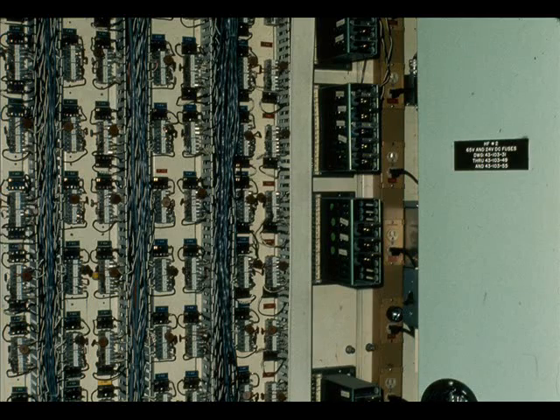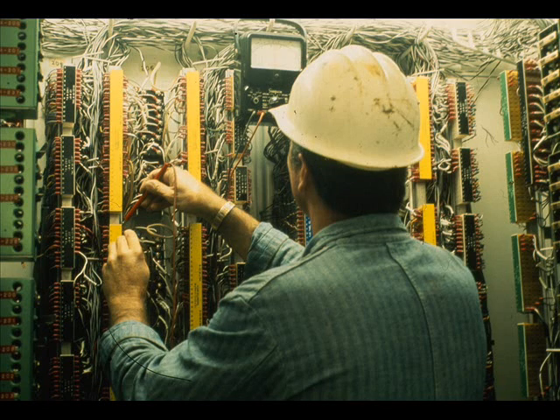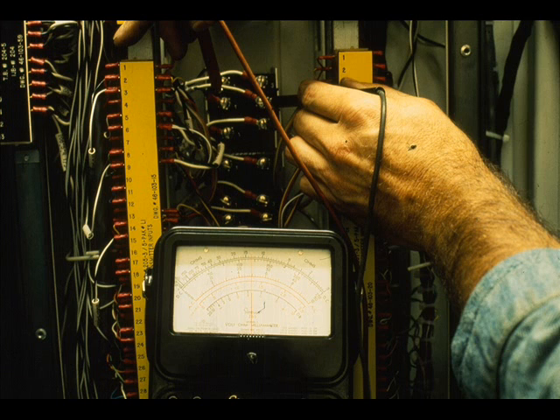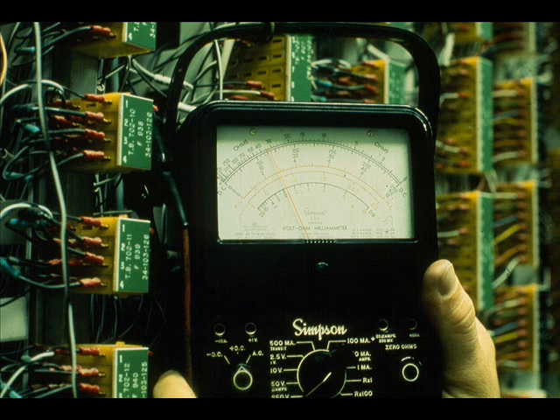Measure the DC supply voltage to the transmitter. We are measuring across terminals 1 and 3 of the input module for this Veritrack loop. The voltage should be 24 volts DC for most 4 to 20 milliamp transmitters. For the Foxboro 10 to 50 milliamp transmitter, the DC supply should be 65 to 90 volts.